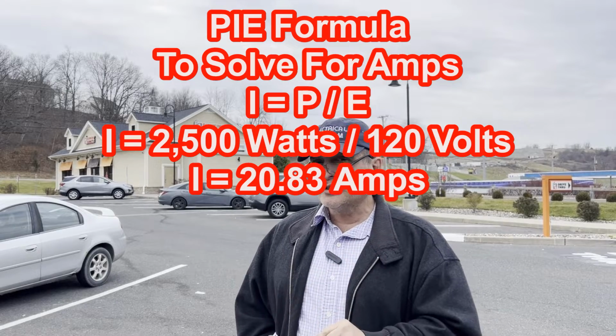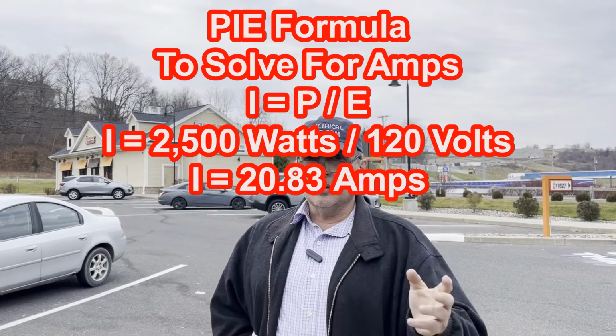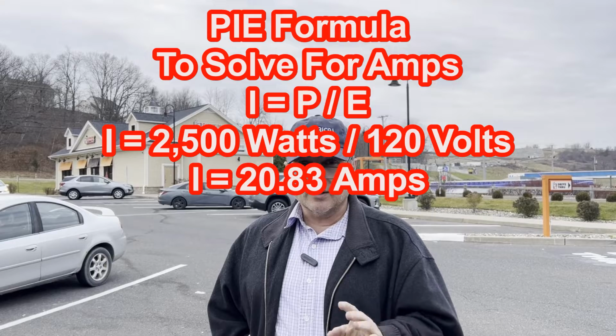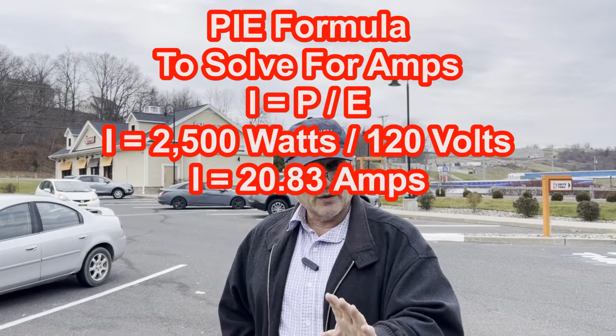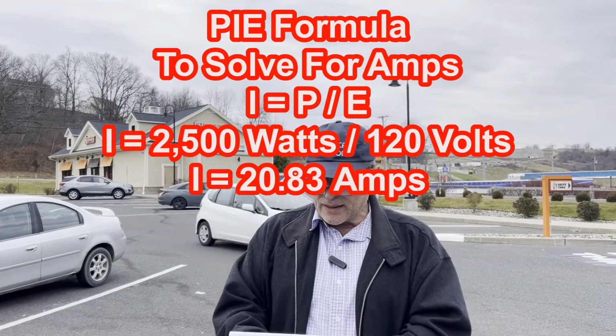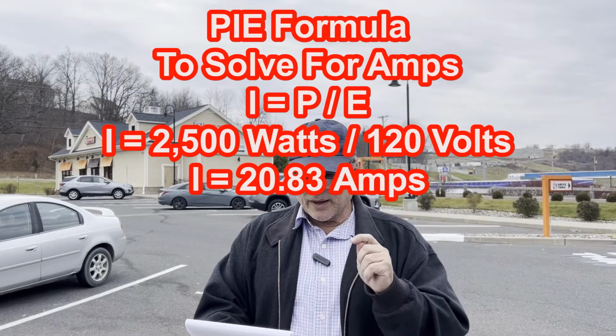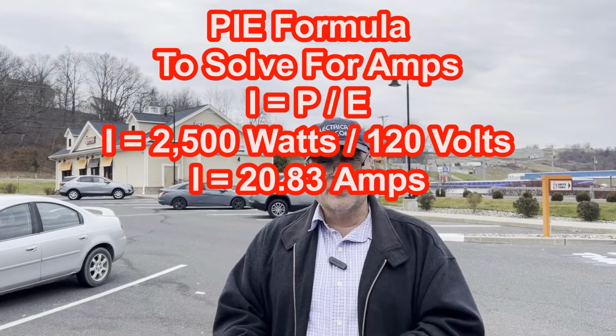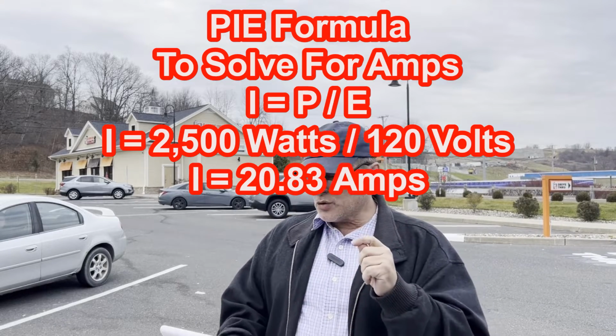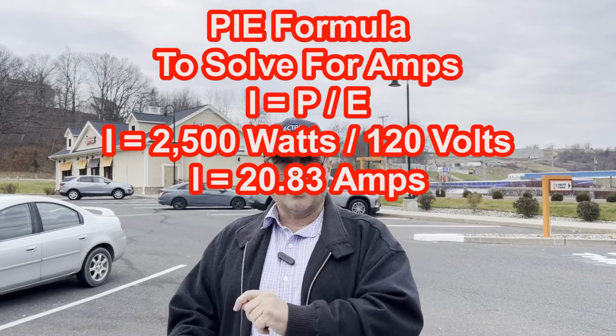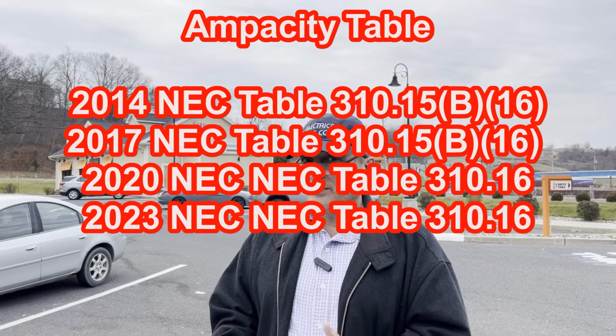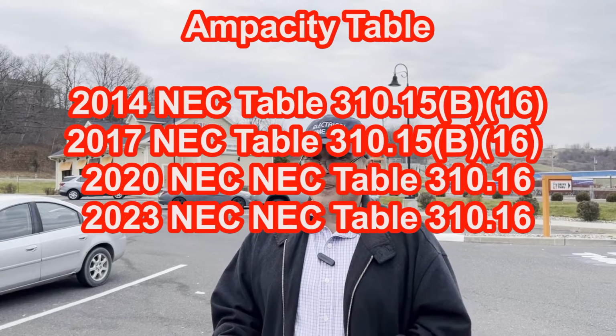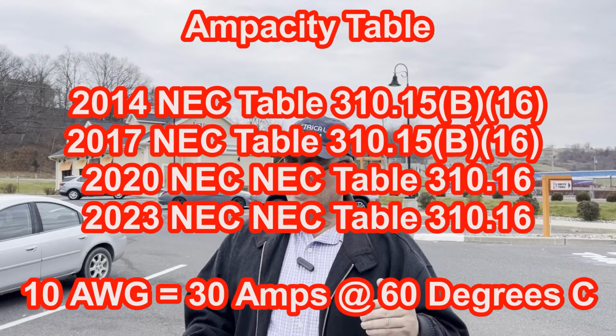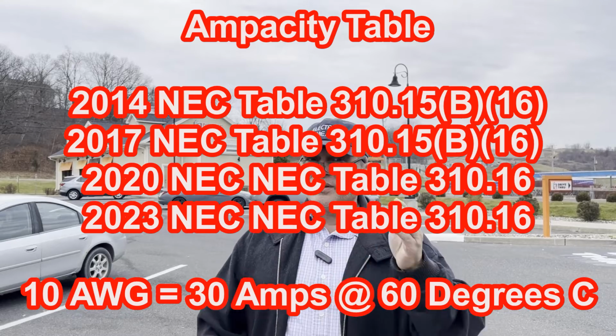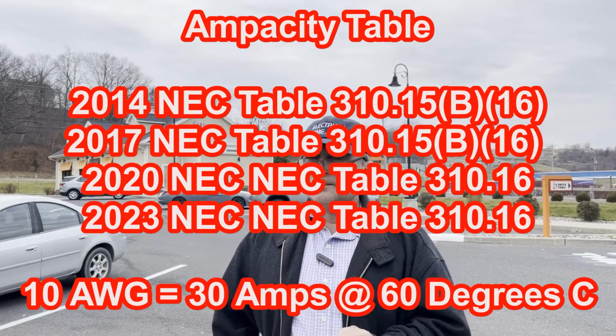I didn't give you the voltage yet, but let's say you only have 120 volts available, right? 120 volts available. And when I did my math, we got 2,500 watts divided by 120 volts. That's 20.83 amps. When we look at our ampacity table, table 310.16, we're going to find 10 gauge. 10 gauge is going to be equal to 30 amps under the 60 degree C column.